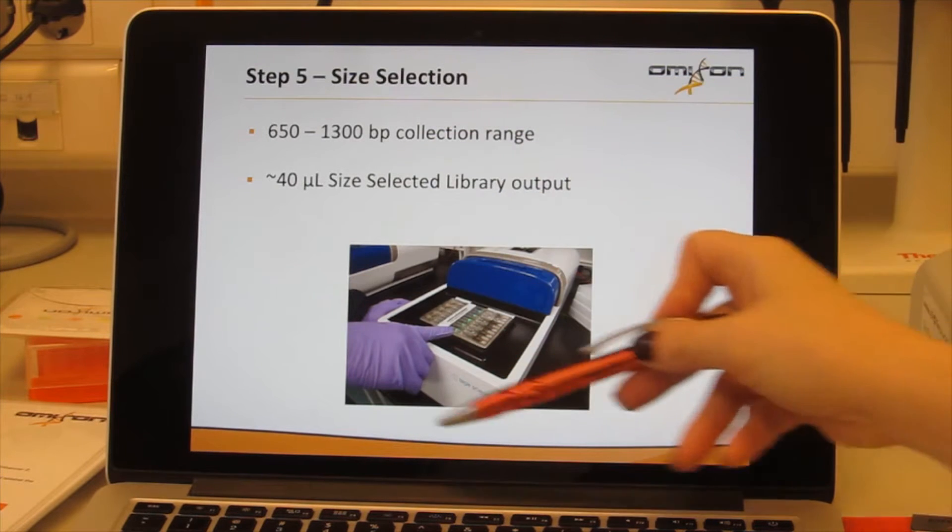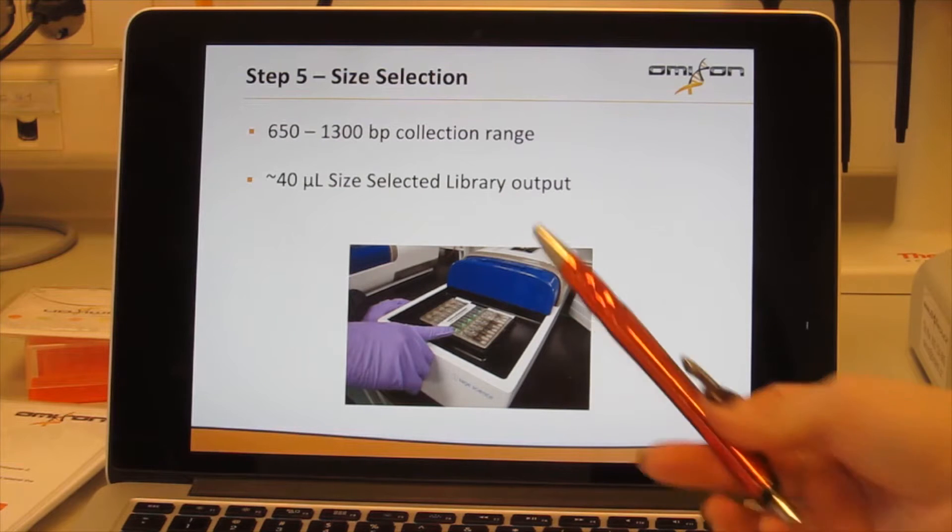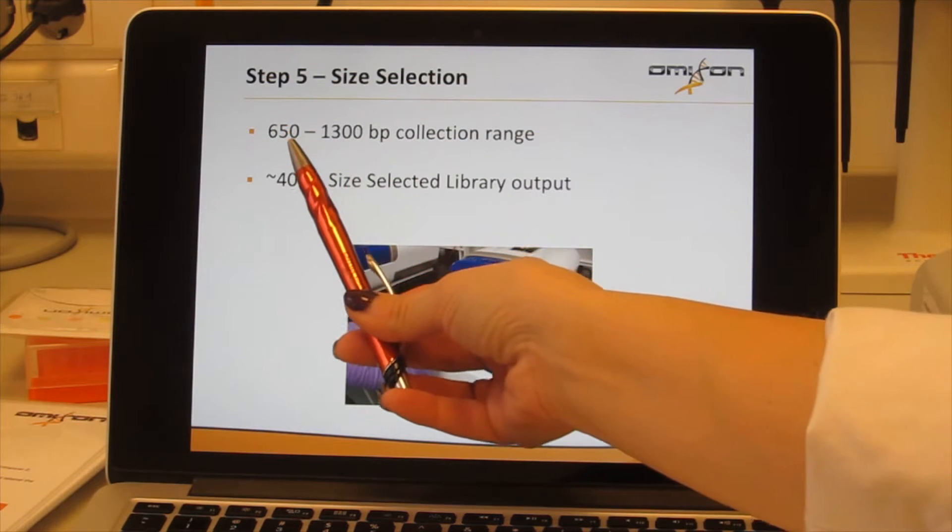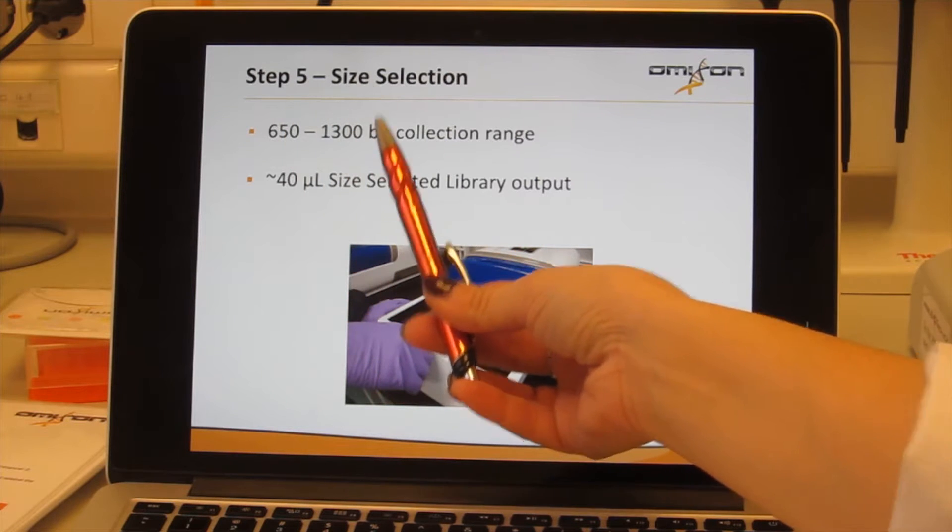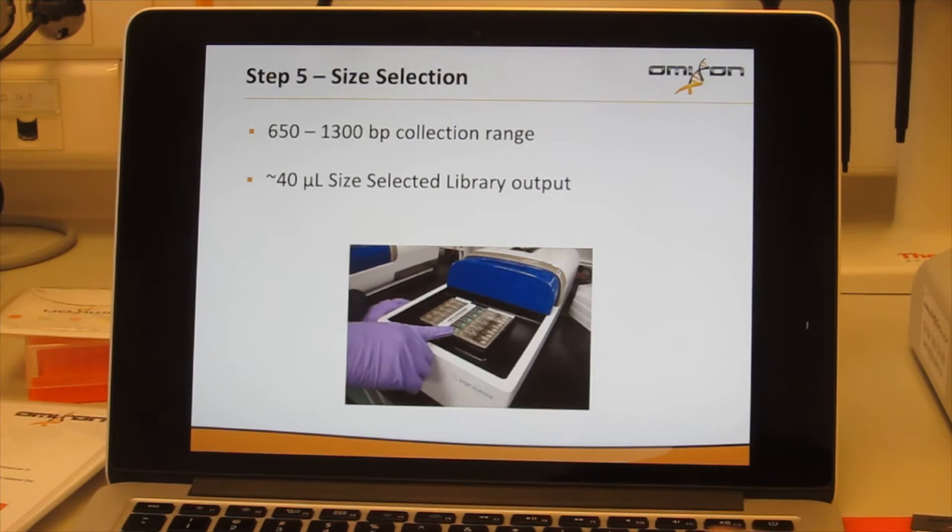Essentially the Pippin Prep machine looks exactly like this, like what you see here in the picture. The collection range that we set the machine up to collect is between 650 base pairs to 1300 base pairs, and at the end of the run we expect approximately 40 microliters of size selected library output.